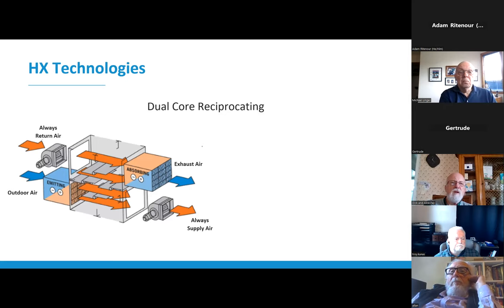And then the last technology is the dual core reciprocating heat exchanger. A couple of key things to note here are that there are two cores. There's an absorbing core that's absorbing heat, and then there is an emitting core that is emitting heat.